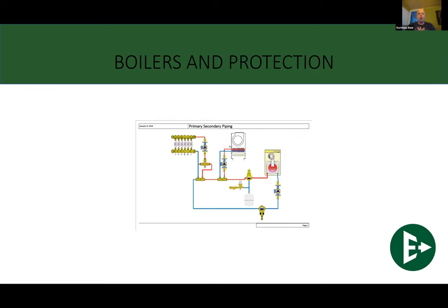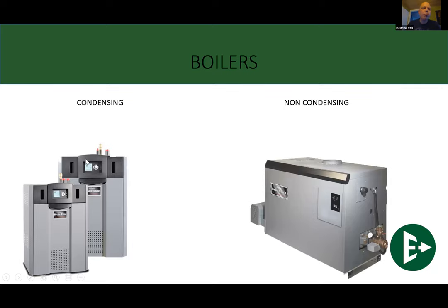All right. So when it comes to boilers, there's two basic schools out there right now. There's your condensing boilers and your non-condensing boilers. Now, your condensing boilers, you're going to want to run them at a nice low temperature to make sure you get that nice cool return temperature. Somewhere below 135 is kind of the magic number to make these things condense. And that's where they get their most efficiency. And they usually vent with plastic venting.